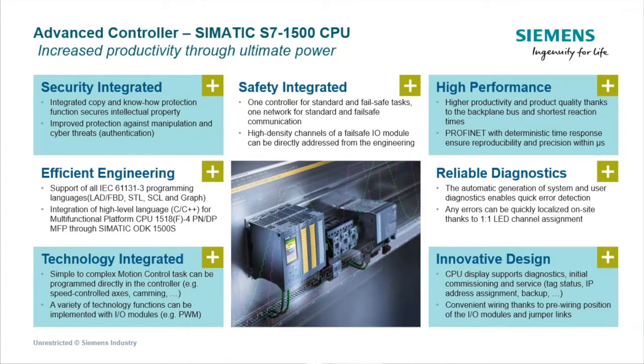I should also mention that the S7-1500 now supports an active backplane bus that allows increased system availability due to reaction-free plugging and unplugging of I/O modules during operation. If one or more of the I/O modules are replaced, the system will remain in run to not stop your control program. The S7-1500 is also a very innovative design.